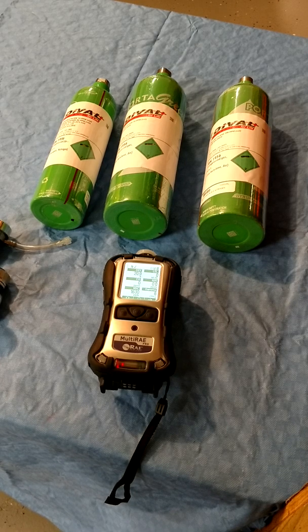In this video we'll be covering the steps to perform a calibration span check on the Multi-Rae Pro. Span calibrations are routinely performed monthly on our portable gas monitors. They are also required if a sensor or the PID lamp are changed, or if a sensor fails its calibration.